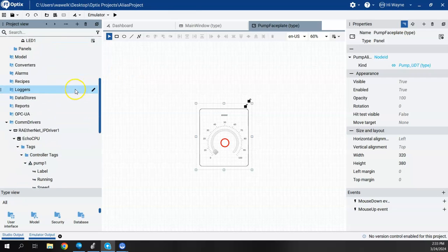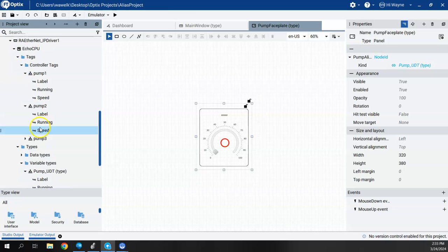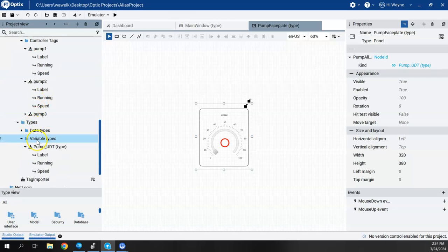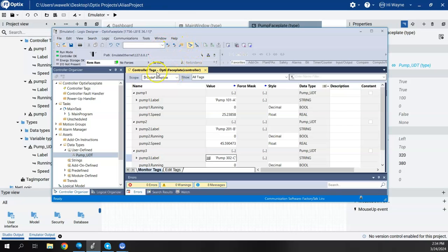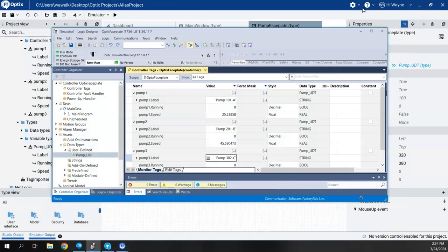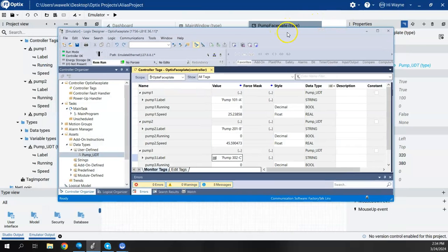If I come over to my com drivers, under my RA Ethernet IP in my Logix Echo, I had types and variable types, and here was my pump UDT type. This was actually coming from a Logix controller. I had Studio 5000, I created a UDT called pump UDT, and I created three instances: pumps one, two, and three. There were basically three tags in each instance: label, running, and speed. I'm using Logix Echo in the background — a real but emulated controller — and Optix is grabbing these tags from the Logix controller.